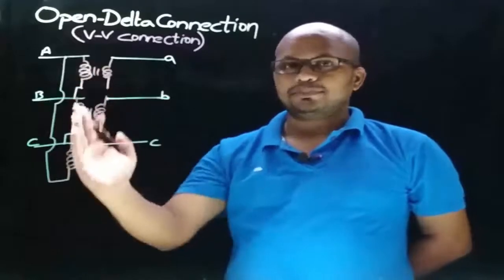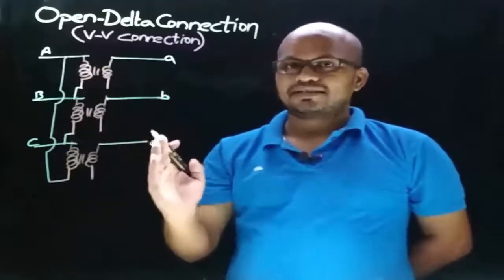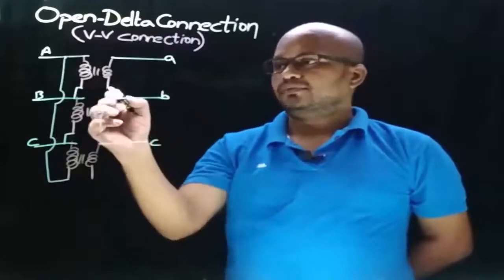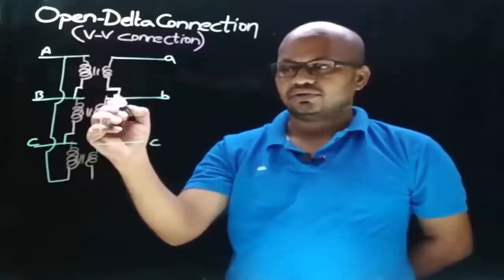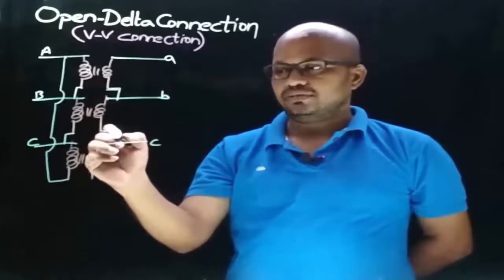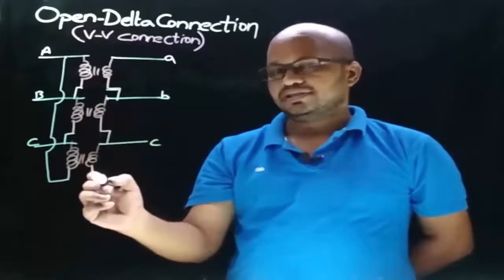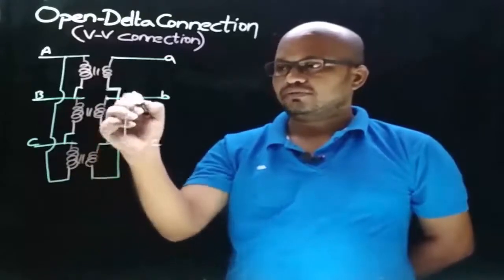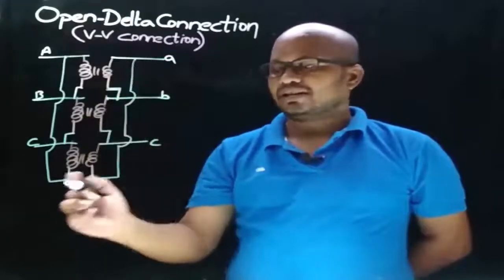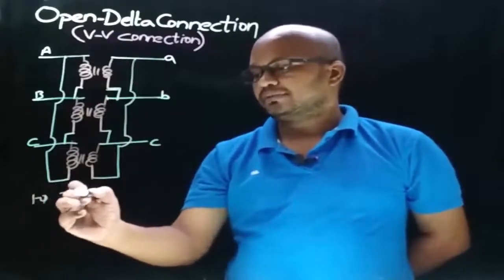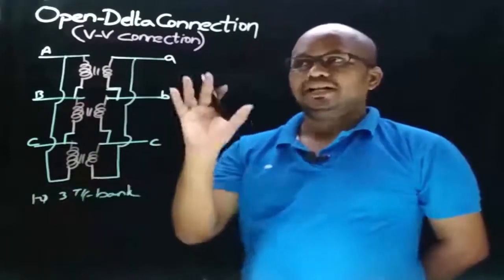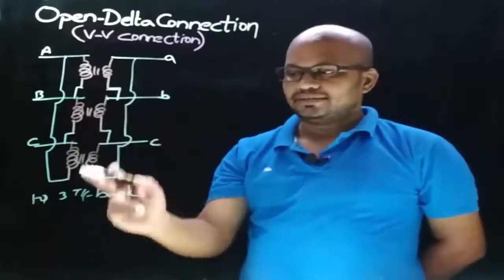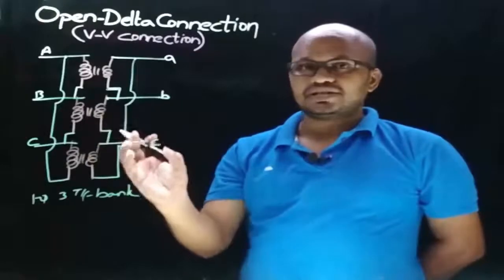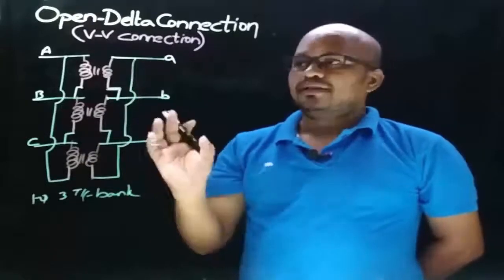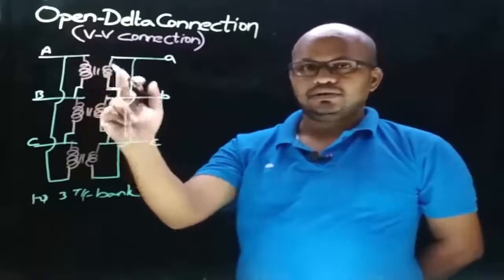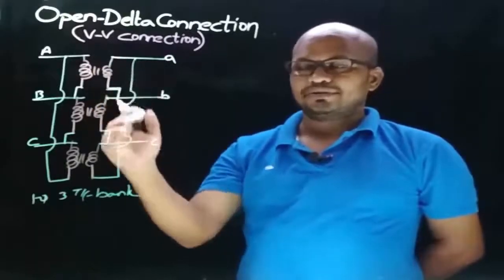So this is how we can obtain delta connection. Similarly, let's obtain delta connection on the secondary side. So the finishing end of one coil is connected to the starting end of the other coil. Here this is the finishing end which is connected to the starting end of the other coil, and this is the finishing end which is connected to the starting end of the other coil. So this is how delta-delta connection is obtained for a single phase 3 transformer bank. Open delta connection means if one of the transformers in this bank gets failed, then the resultant connection is called open delta connection. Let's consider transformer 1 got failed, and now let's observe the connection.